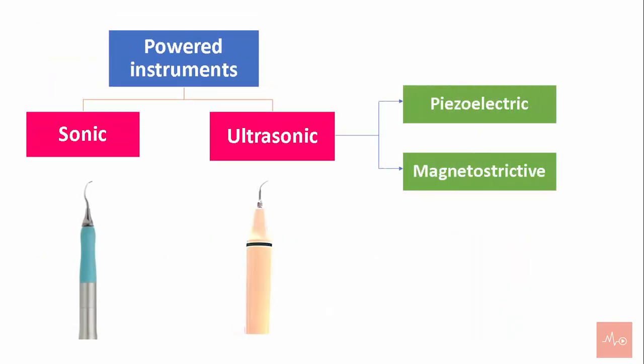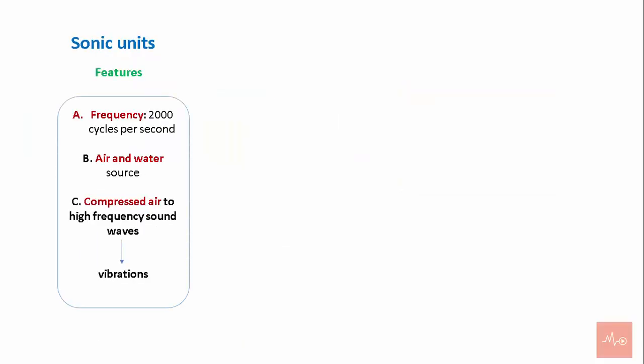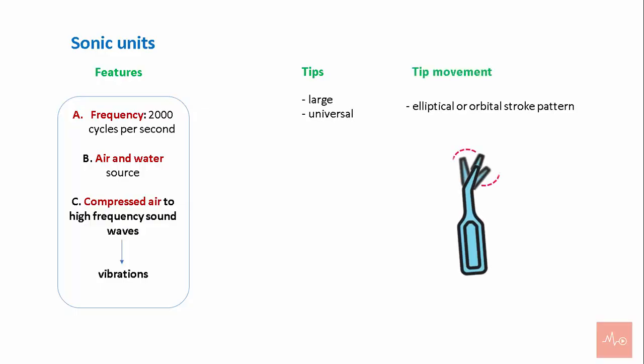Powered instruments can be sonic or ultrasonic. Sonic units work at a frequency of 2,000 cycles per second and use compressed air from the dental unit and water as a source. The compressed air is converted into high-frequency sound waves that create vibrations. The tips used are large and universal in design, with an elliptical or orbital stroke pattern, allowing the instrument to be adapted to all tooth surfaces.